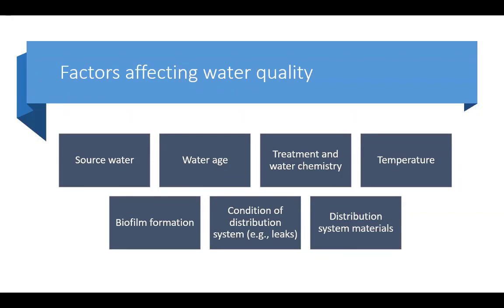And if you look at the lecture from 483 from Wednesday, you'll see some photos in that showing the extent of the corrosion. These photos were actually taken in Holmes Hall after the reverse osmosis unit, where there was significant corrosion of the iron pipes.